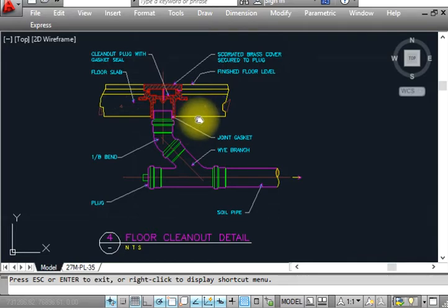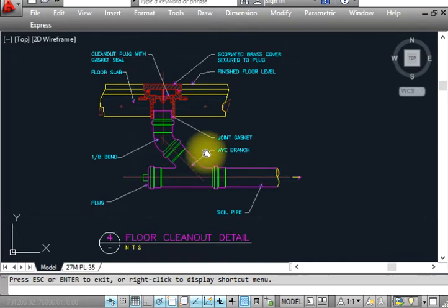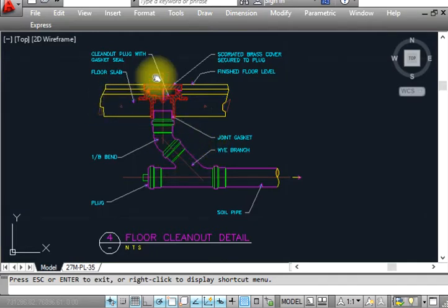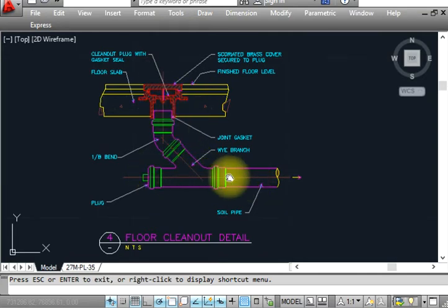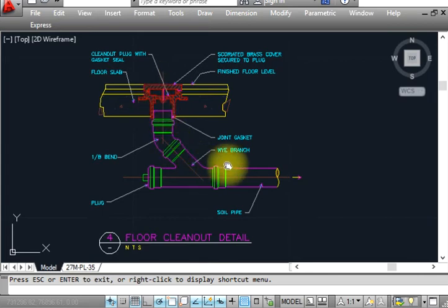This is the floor drain. Let me explain the difference between floor clean out and floor drain. Floor drain will be open all the time — water will drain from there and there is a P-trap, so smell will be stopped and will not come outside the toilet or kitchen area. Clean out is just for cleaning purposes — at the end of the pipe you must provide a clean out as per plumbing code. You clean it with a wire.